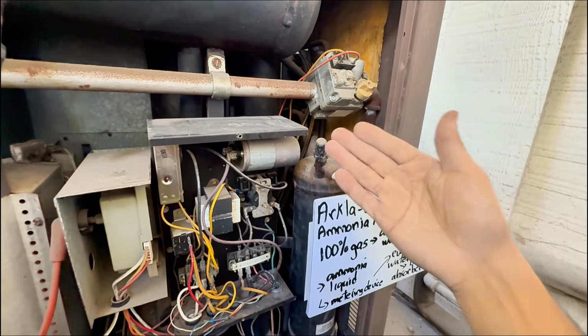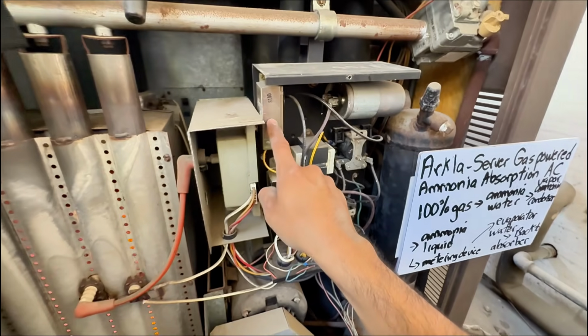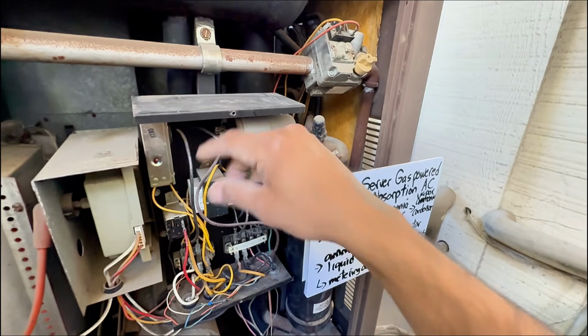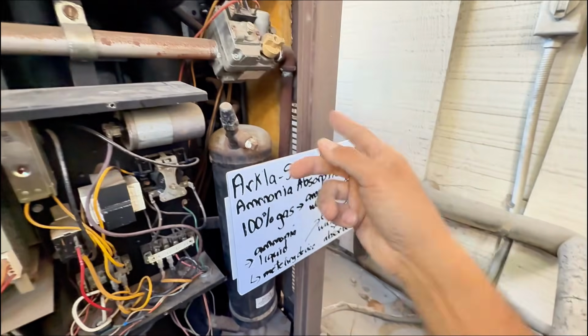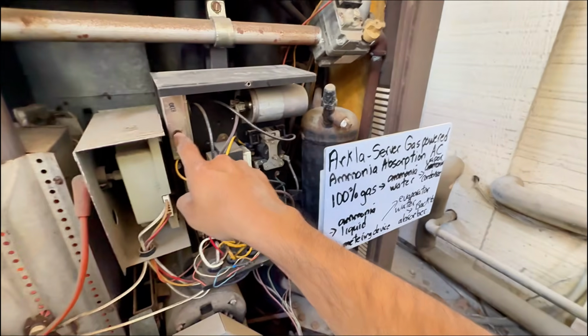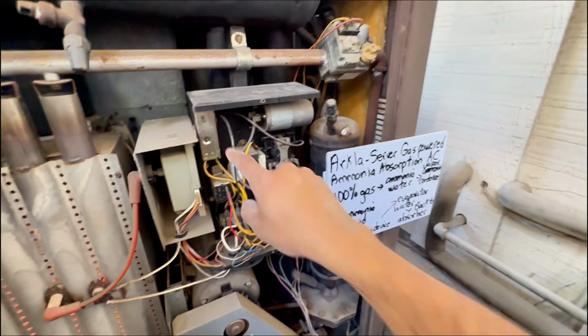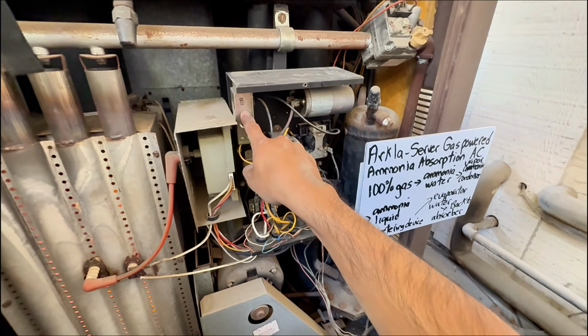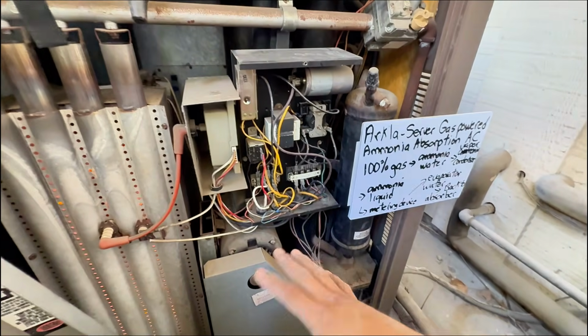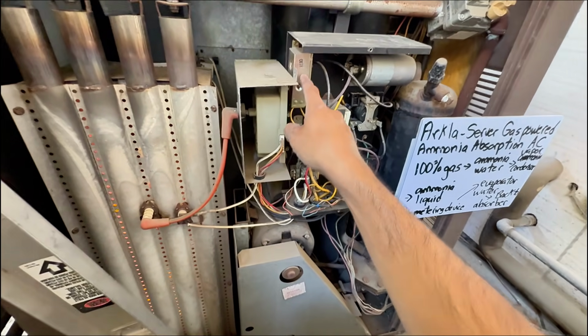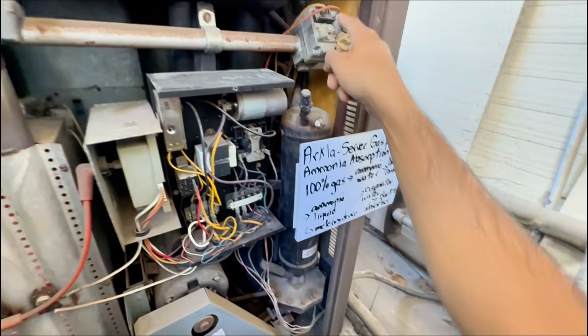Unless there was not a call for cooling. You actually have a time delay right here. So unless there was not a call for cooling and I have to go back inside and check, then it could have happened where I didn't have a call for cooling no more, but I have a timer delay where it keeps everything on for about 90 seconds and then it shuts off, at least when I researched this. So it could have been the gas valve, and I should have checked it right now before that was off.